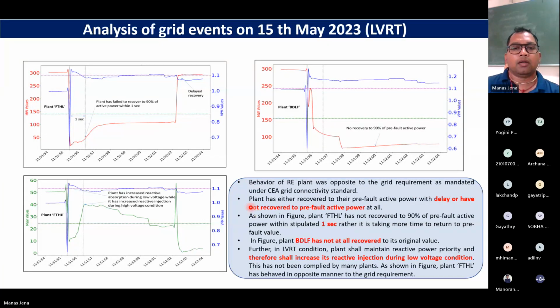what we have mandated. The plant has either recovered to its pre-fault active power with a delay. Okay, this plant has recovered but with a very substantial delay, or has not recovered. This plant could never recover. Then plant FTHL has not recovered to 90% of the pre-fault active power within the stipulated 1 second, in this scenario. This BDLF has not at all recovered. Further, in LVRT condition, plants shall maintain reactive power priority, and therefore shall increase their reactive injection during low voltage condition. This has not been complied with by many plants. As shown in the figure, this particular FTHL plant has behaved in the opposite direction.